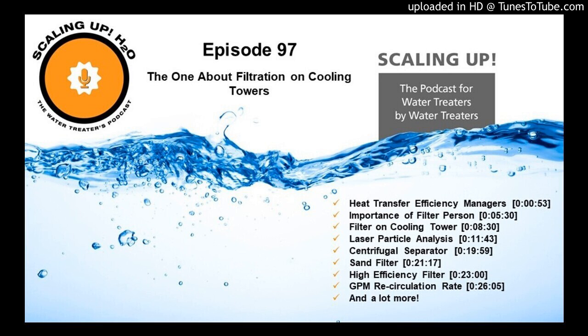And so what that does is when you design a filter, you design it with a particular pump and a particular head to get a particular gallons per minute through the filter. And so if you've got varying pressures in and out of the filter, that means you have to add valves, adjust pressures and the rest. And it's very hard to control a filter flow rate through the filter unless you've got pressure the same in and out of the filter. So that's what we generally design.